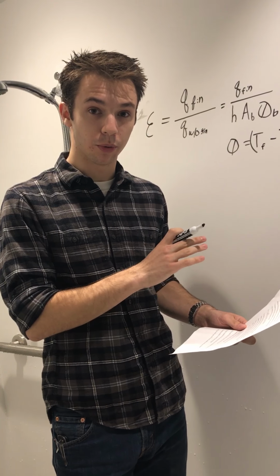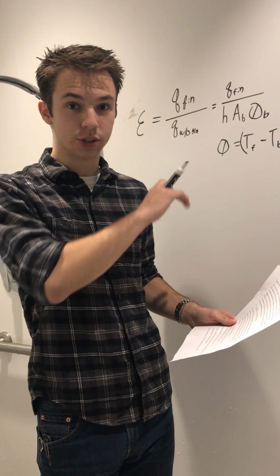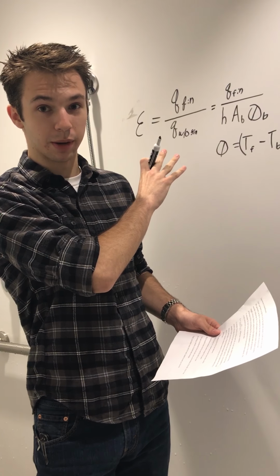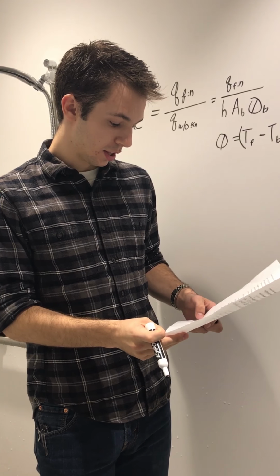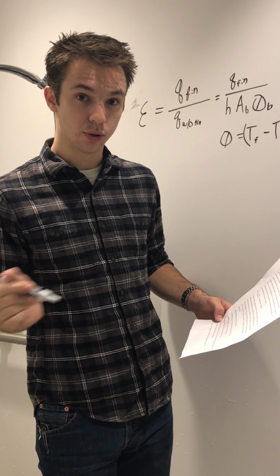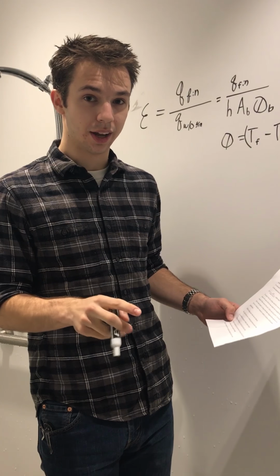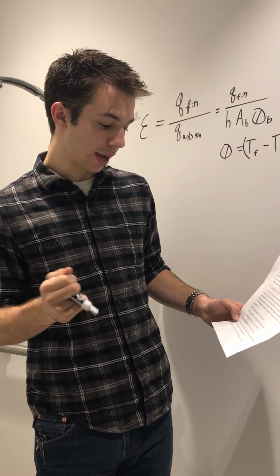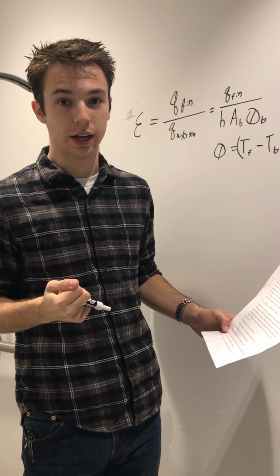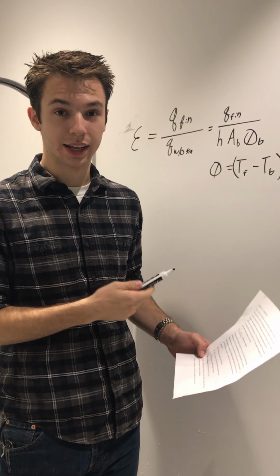Combustion creates gases that rise through our flue. These gases transfer heat through the fins that we talked about, which then transfers to our fluid. The heat transferred to the cold fluid causes a density change in the fluid, and it rises through the tank. This creates a pseudo-co-current heat exchanger effect. Finally, the heated water exits the tank to your shower.